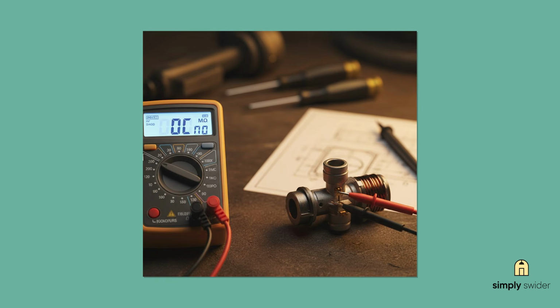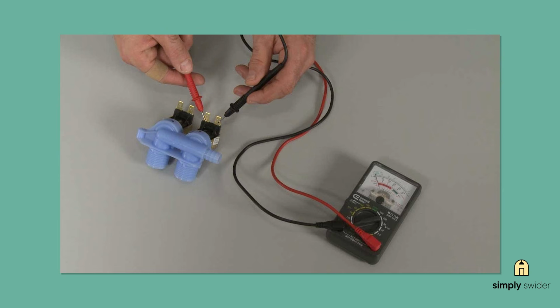If that doesn't work, grab your multimeter and test the resistance on those valve coils. You should see between 500 and 1500 ohms. If you get a reading outside that range or OL on your meter, the valve's shot. Here's the tricky part. These valves can test good with your multimeter, but still fail if the control board isn't sending the required 120 volts. Testing live voltage requires working around electrical components while the machine is plugged in. If you're not comfortable with electrical work, this is where I'd recommend calling a professional.